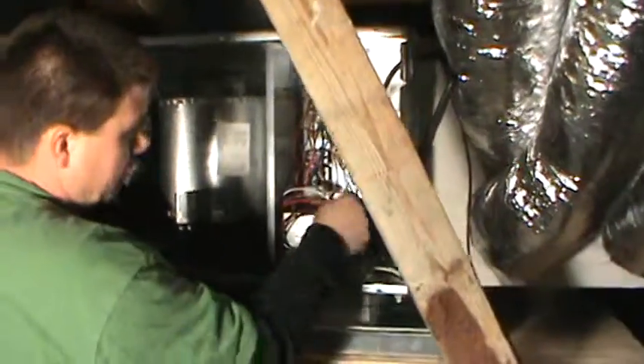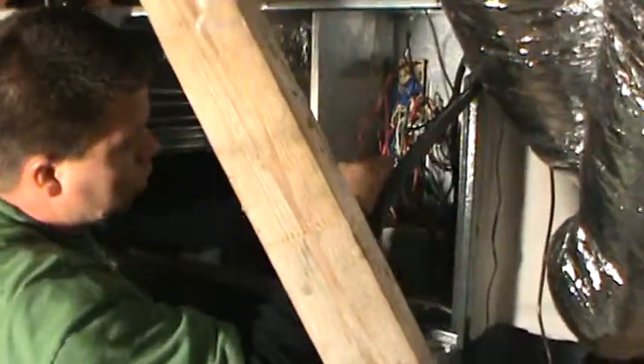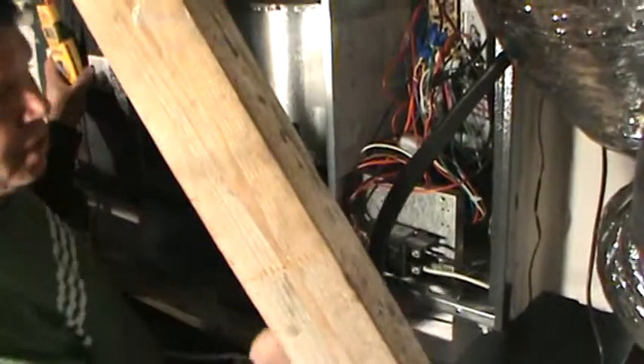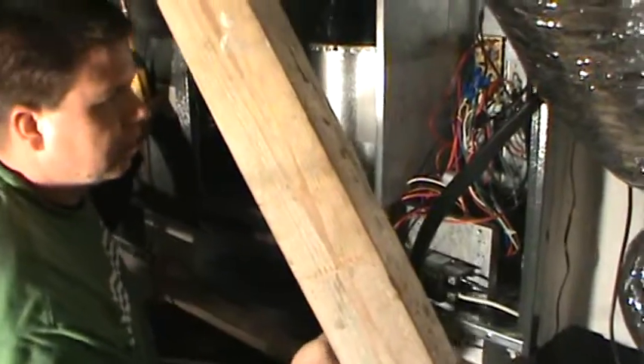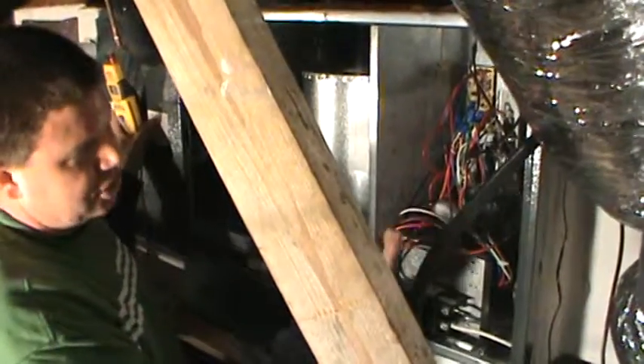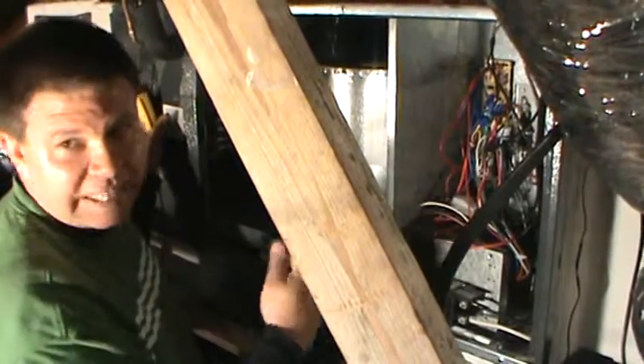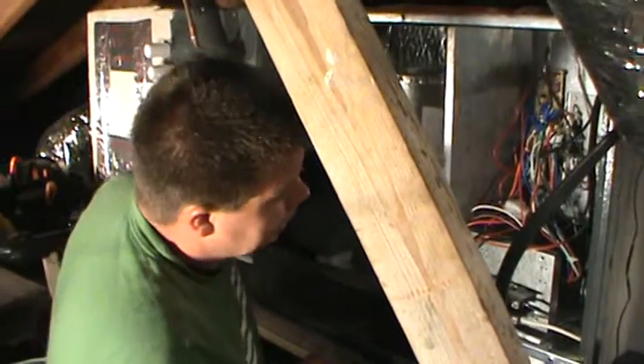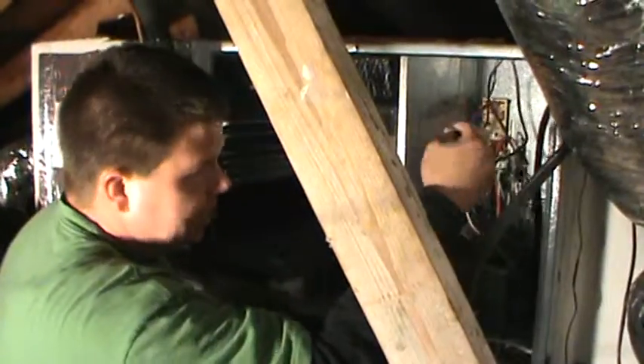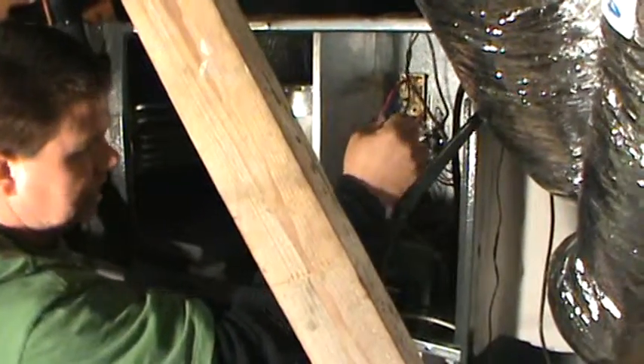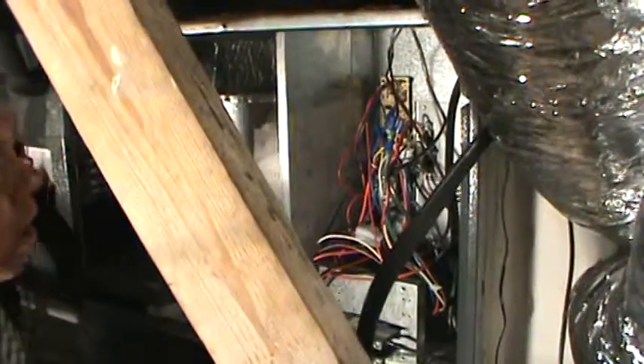any melted wire ends. If you see them going into the boards or into your heat strip, and that you see the bubbling of the plastic, the insulation on the wire, then you need to cut that wire back and put a new terminal on it. And again, just make sure all your wire nuts are nice and tight. Look for any frayed wires. Make sure where your wires go through the units are not vibrating and rubbing a hole inside them.